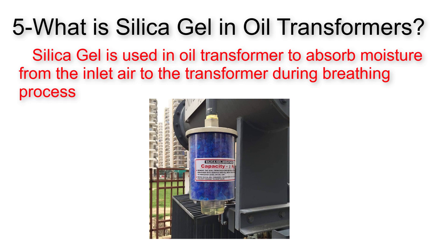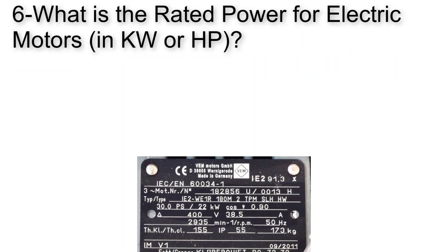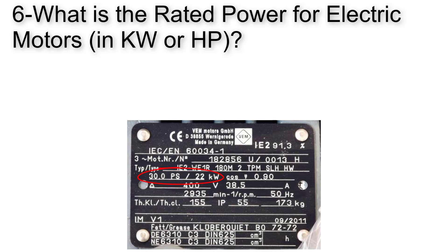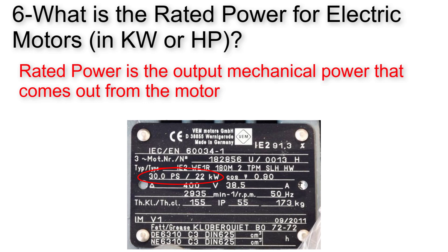Another question: what is the rated power in kilowatt or horsepower shown on the electric motor nameplate? This is a simple yet tricky question. The rated power on the nameplate represents the output mechanical power coming out of the motor — not the input electrical power. To calculate the input electrical power, we need the efficiency factor.